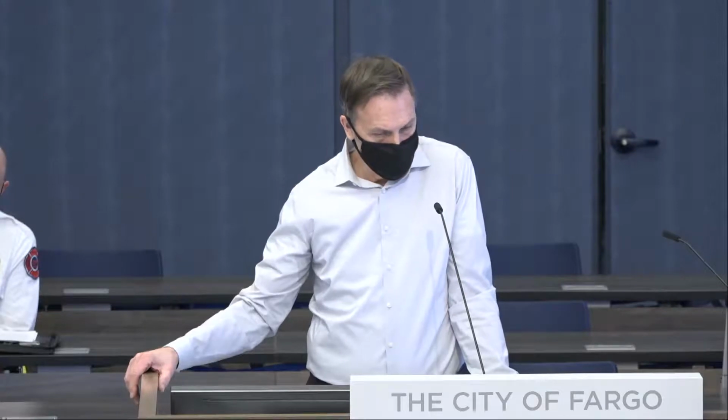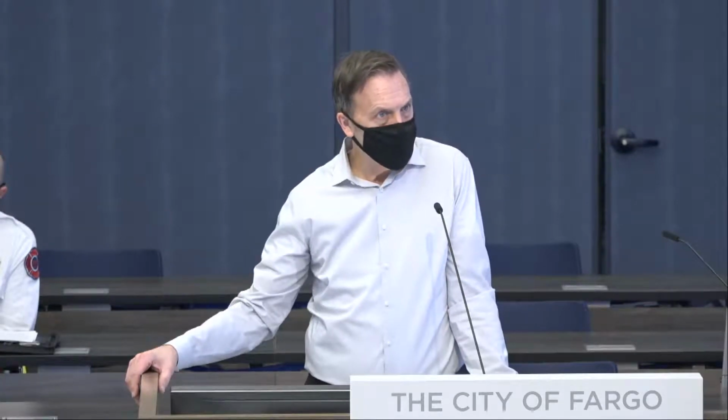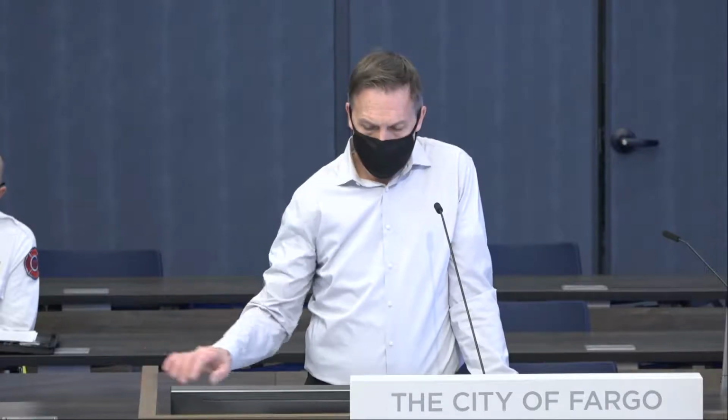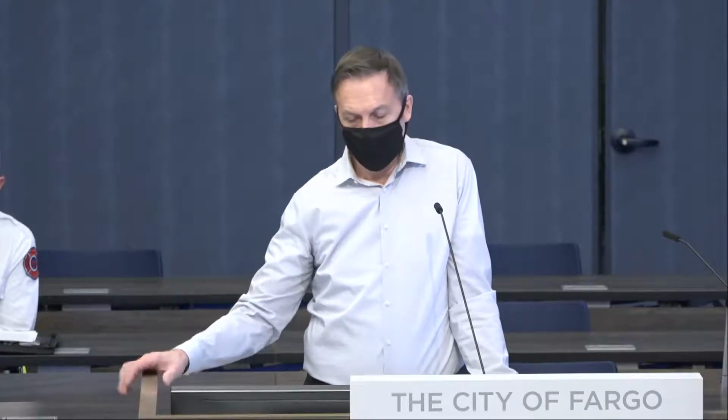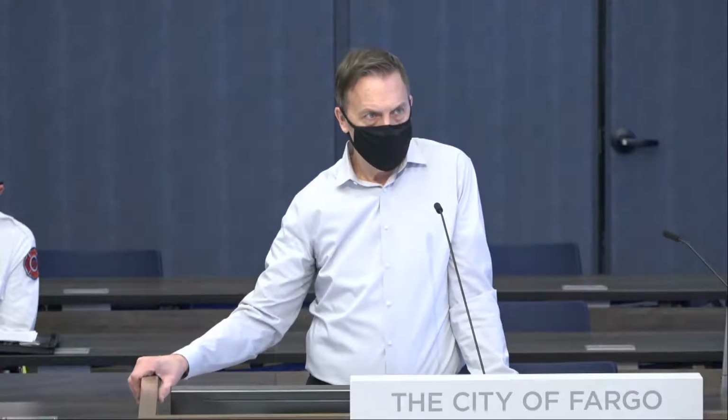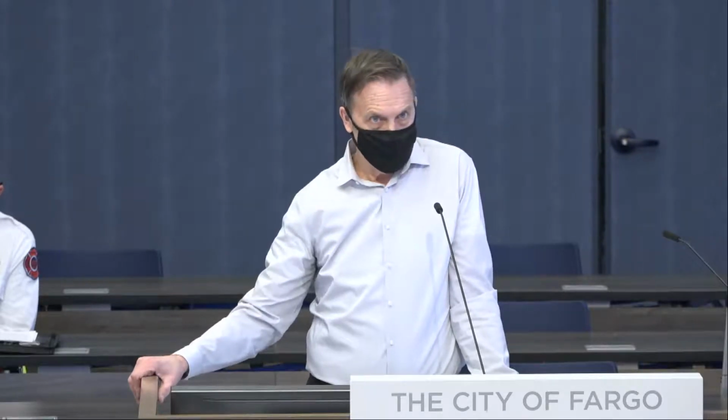That's a good point. I said this is 1A or 2A construction, 1 hour. It is not a fire barrier. Tom Smith said it's a fire barrier. It's not. It's 1 hour construction. You could put a hole right next to that garage. The owner could take out a parking spot and put a hole right in that parking spot, because it's not a fire barrier. It's 1 hour construction, and it's different than fire barriers.